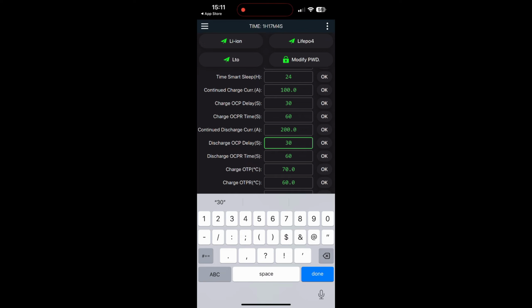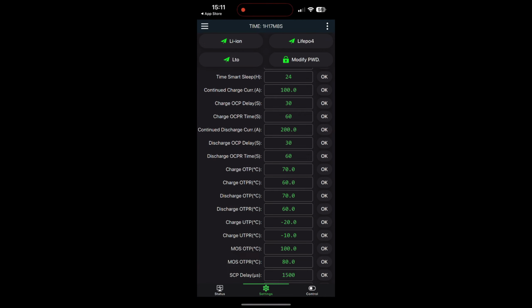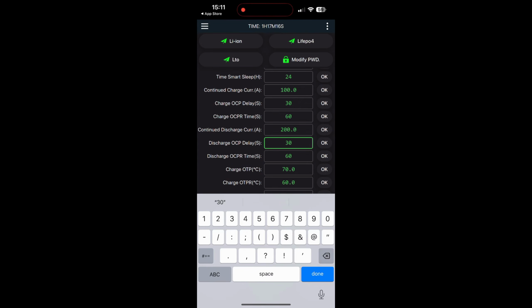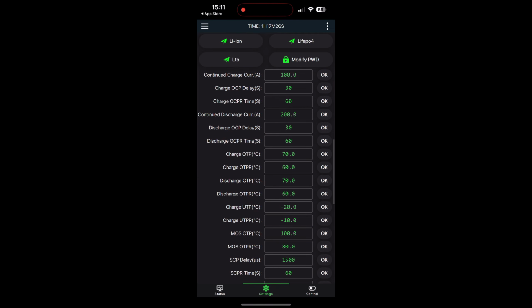So it currently is set to 300 seconds, which is weird. So I'll change that to 30 seconds. Again, it'll sustain 200 amps for 30 seconds. After the 30-second period, the BMS will disconnect. It will then wait 60 seconds and then it'll allow discharge to continue.